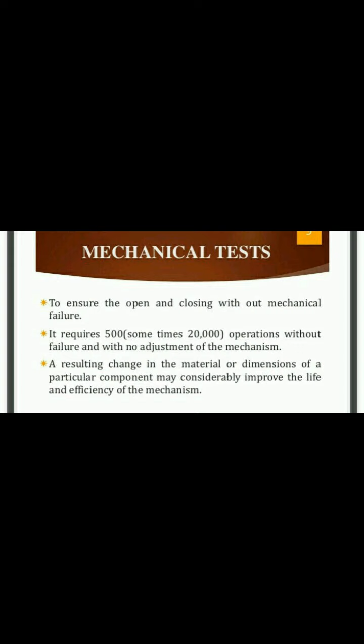The name itself indicates its meaning, because a circuit breaker is an electromechanical device. So there are different mechanical parts. The understanding point of a mechanical test is to ensure opening and closing without mechanical failure. It requires 500, but sometimes 20,000 operations without failure, with no adjustment of the mechanism. As a result, a change in material or dimensions of a particular component may considerably improve the life and efficiency of the mechanism. So this is called the mechanical test.